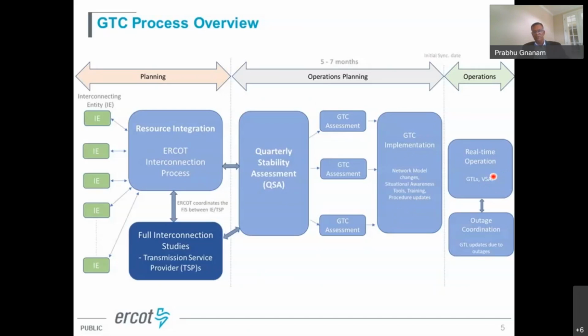One of the tools we use is VSAT. That's a separate tool, but the GTCs and GTLs, generic transmission limits, are based on a static table which comes out of this process. One thing I want to point out is outage coordination. Anytime we have planned outages, we have to update those static limits, because the static limits are only performed for what we call base case N-1 and some prior outages N-1-1.